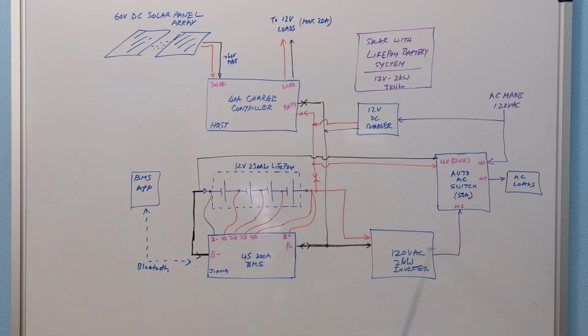The inverter drives an automatic switch which senses the battery voltage right across the battery. If it falls below 12 volts or so, this will switch to the mains and then drive the AC load. Once the voltage on the battery rises above 12.8 volts, it switches back to the battery and disconnects from the AC mains, and then the inverter drives the load. That way I keep this system in a fairly good operating range without over discharging the battery, while also maintaining uninterruptible power supply to the AC load.